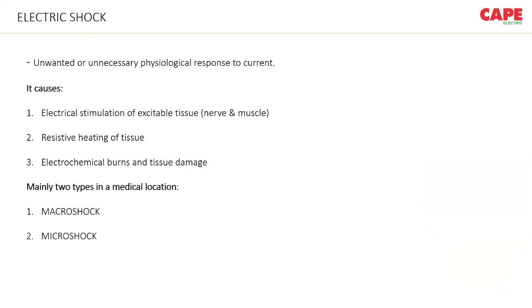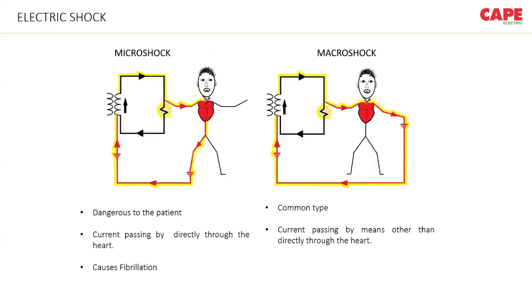There are mainly two types of shocks in the medical location. One is a macro shock and the second is a micro shock. These two shocks are commonly found in medical locations. Macro shock is the common type of shock where the current takes a path other than the heart. Relatively, it is less dangerous to the patient. It is less dangerous, but it doesn't mean that it is not dangerous. It is less dangerous because it can cause burns.